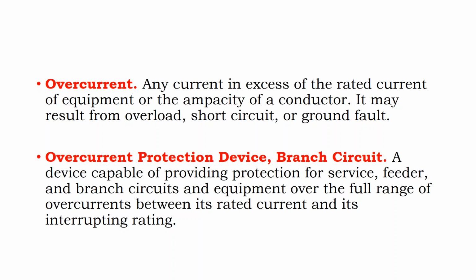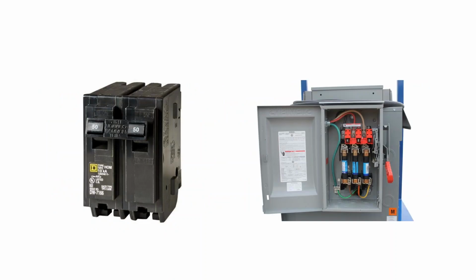And so there are some advantages of having a fuse that during an overcurrent condition will just burn up and then not work anymore until someone comes out and actually looks at it, rather than just having a client be able to reset the switch and see if the problem happens again. And where I've seen this happen is up on the rooftop in your combiner box, where you have, and this isn't very illustrative of it, multiple circuits going into the box being combined into one set of wires going back to the inverter.